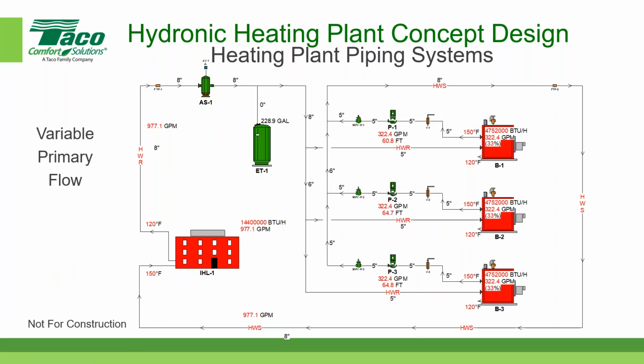Can we have different delta T's for primary and secondary loops? You can, yeah. Generally speaking, the secondary loop is going to have a lower delta T than the primary loop, if you have different ones. If you want to have a difference, yeah.